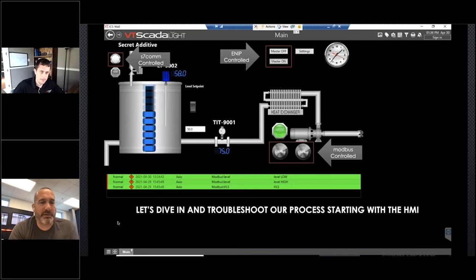Here's a human machine interface, or HMI — this is where the operator gets a graphical view of the process. We have our tank with the level on it and the on/off controllers for the pump. We're interfacing this HMI with multiple different PLCs: Modbus, S7com, and Ethernet IP. If somebody gained access to the HMI via local or remote means, they can control the entire process. Our alarms and reports are created from this asset, so it's a pretty important asset to protect. If you shut this off while your process is running, you can't control your process or know what the set points are.